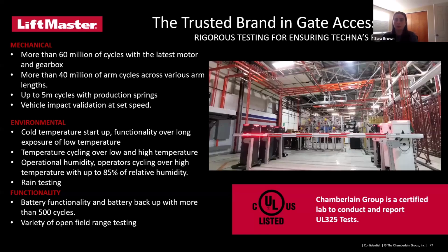We do have temperature and humidity cycling chambers. We tested this with heaters down to negative 40 degrees Fahrenheit, as well as up to 140 degrees Fahrenheit, with up to 85% relative humidity, and then the rain again.